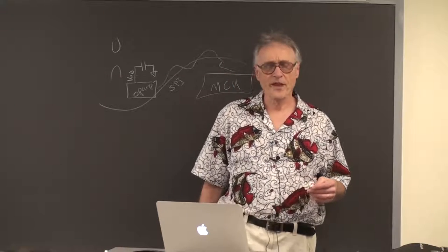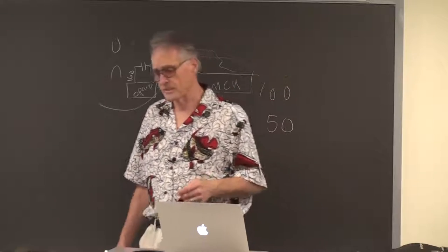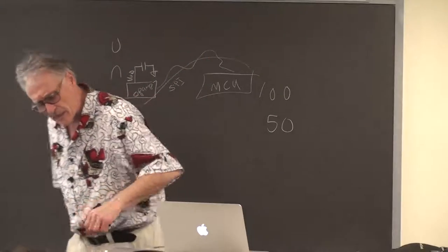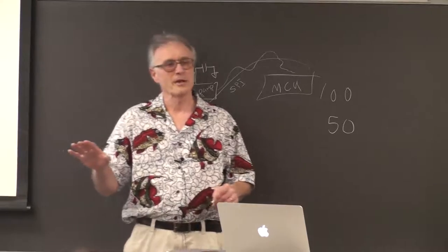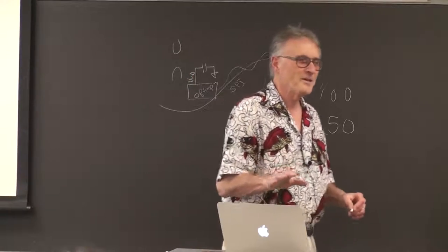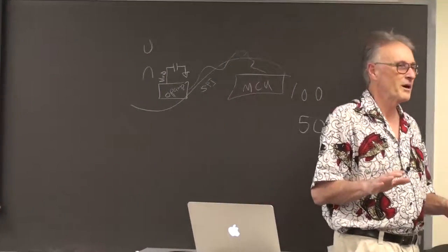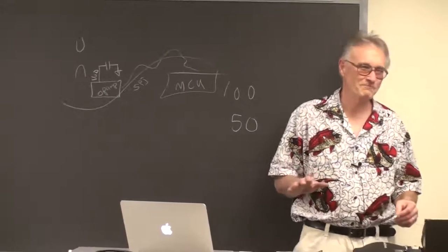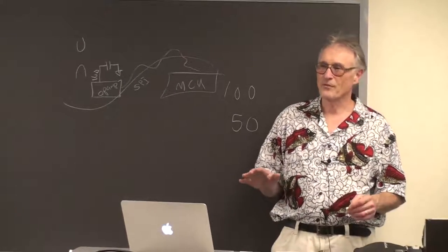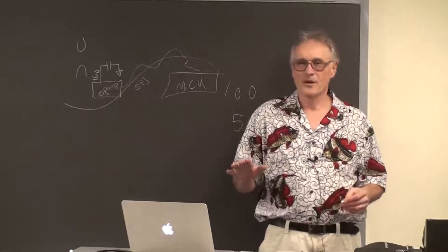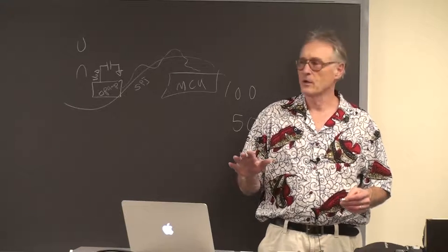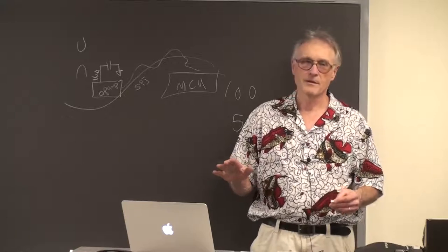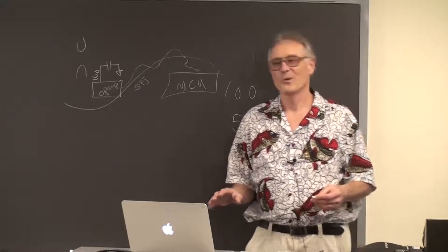We got a batch of fans in. I bought some extra fans. Turns out the fans, even though they're the same model from the same manufacturer, don't have the same controller in them, and they won't work with pulse width modulation. So I've got 20 fans sitting up there that only work if you set the PWM to lower than 30 hertz, which I suppose you could do.